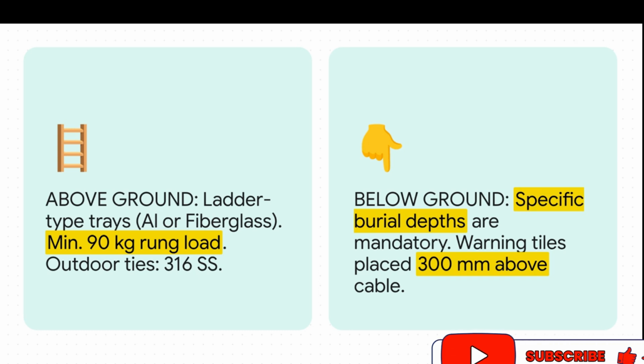For outdoor trays, your cable ties have to be nylon-coated 316 stainless steel. Then, when you go underground, it's all about depth and protection. The burial depths aren't suggestions, they're mandatory. And you have to put those red warning tiles exactly 300 millimeters above the cable.